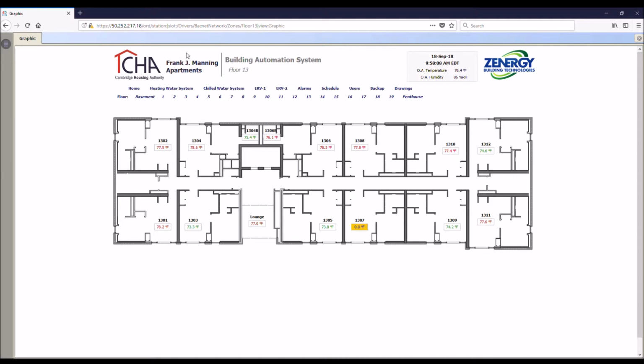But if we saw that the same room on every single floor had an issue, well, now we know there probably is an issue with that network. So either a wire got cut, or one of the communicating thermostats is damaged and affecting the network, or there's a power loss down at the main control panel, or the entire network lost power. So you can use these colors, the background color, as a way to troubleshoot what's going on if you have a communication issue.